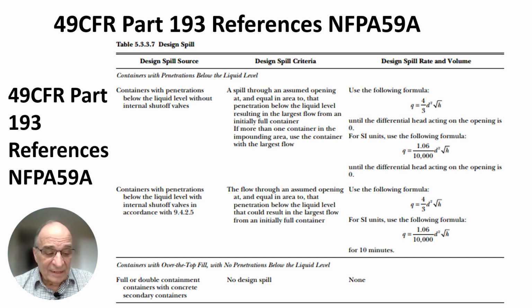Okay, design spill. A calculation method is shown here, and it assumes that you start off with a fully, right to the brim, filled LNG tank, and you have a guillotine cut of a bottom penetration. For the first case, we're going to look at no internal tank valve. You have a formula for the flow rate of LNG that comes out of that tank, and that formula is to be used until the tank is fully emptied or until there is zero differential pressure acting across that bottom inlet and the outside. So that is a total emptying of the tank into your dike area, and that would be your design spill for a tank without an internal tank valve.